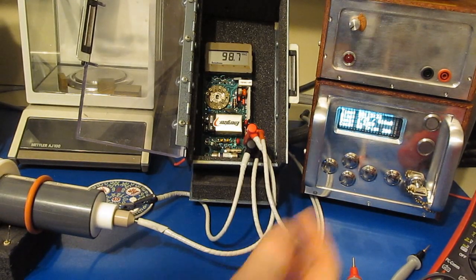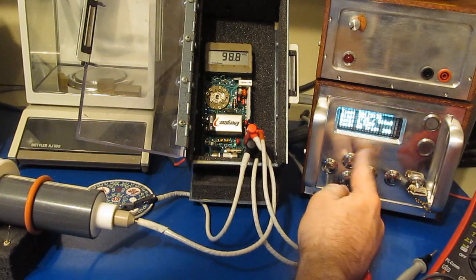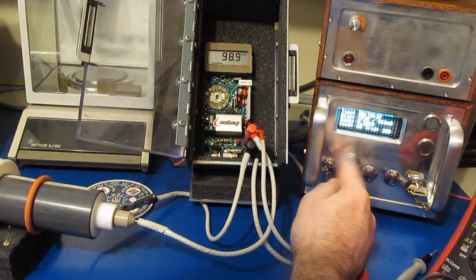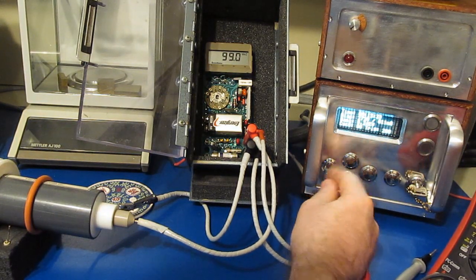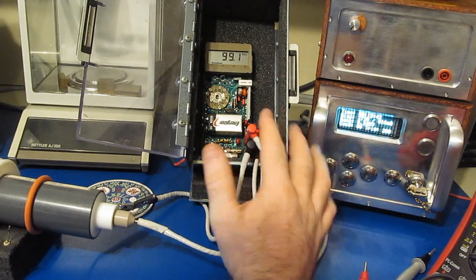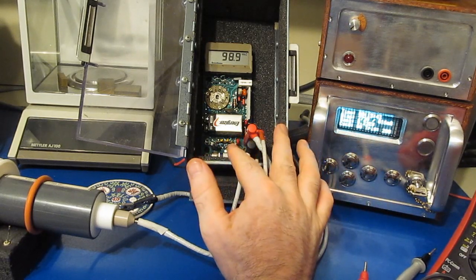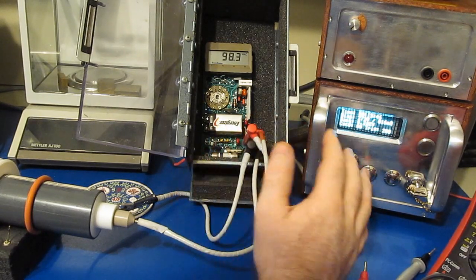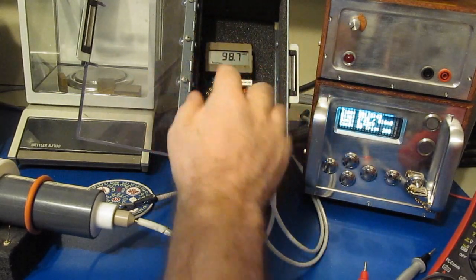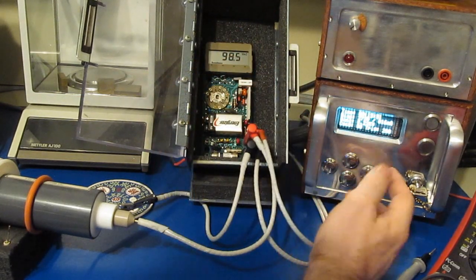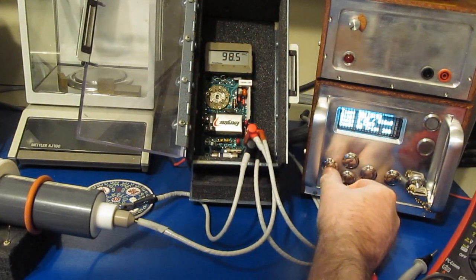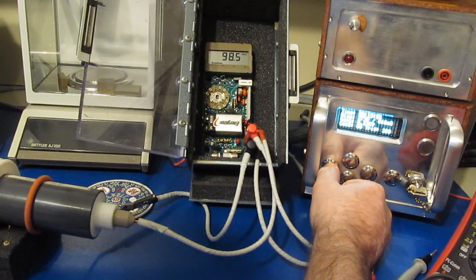Again, the transient generator - the way this works is when the transient is actually applied to the meter, the transient generator turns off the AC output, and then once it's done with the transient it re-enables it. So that's probably why we see this flashing on the meter. Let's go ahead and we'll turn up the voltage in this.